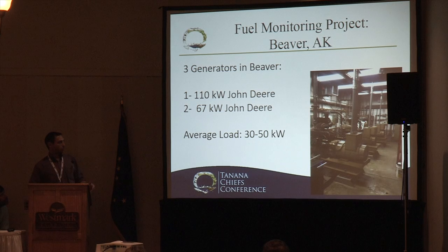We had some funding and were able to work with a distributor out of Seattle that has very high accuracy flow meters called Coriolis flow meters, used a lot in the shipping industry. Shipping and rural islanded grids aren't super similar, but they both have onboard generators and both go through a lot of diesel. So borrowing from an industry really concerned about fuel flow and using it in rural Alaska maybe makes sense.